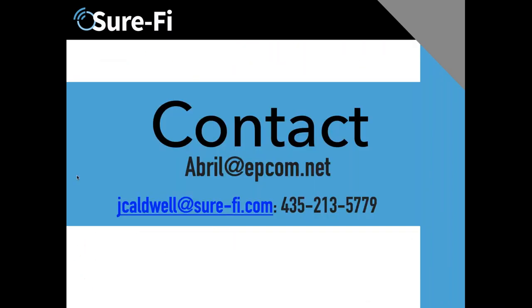Now Mario asks us, what is back-to-back in the middle about that question? I think the back-to-back in the middle just means that they're right next to each other. That is correct. We just usually will put those in the same box and wire it right next to each other. So all your inputs to the outputs, both Wiegand and relay, make it a seamless transition to the next set, either for increasing the distance, or because at that location you need to do some things as well. You might have a gate operator and an RFID reader that are a distance apart, going across, let's say, a cobblestone or a stamped road that you don't want to drill across, and then you go out to the controller as well. So sometimes you want three locations all to have similar controlling, and you can do it there with the daisy chaining of the Sure-Fi units.